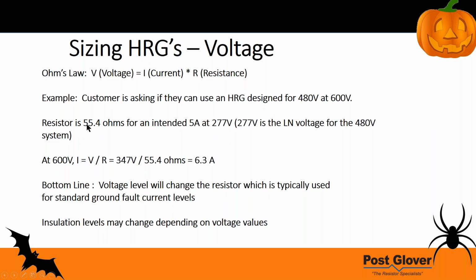So what happens is you have a 55.4 ohm resistor intended for 277 volts line-to-neutral, which gives you 5 amps. At 600 volts line-to-neutral, you're going to have 6.3 amps. So not only are you running a little hotter than usual—and honestly, theoretically you could do this, with our system you could do it, you'll just run hotter than you're supposed to—but you're not expecting it to be 6.3 amps, and that throws off all your current.